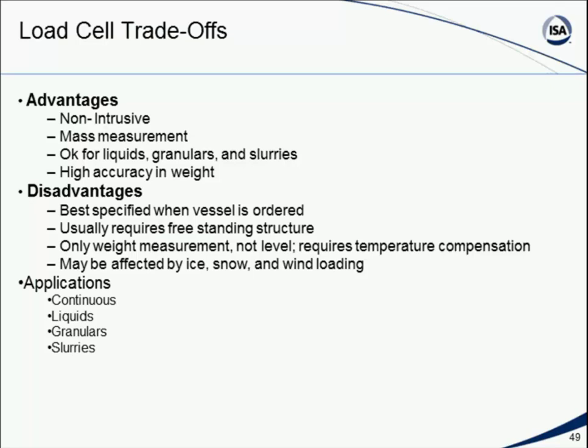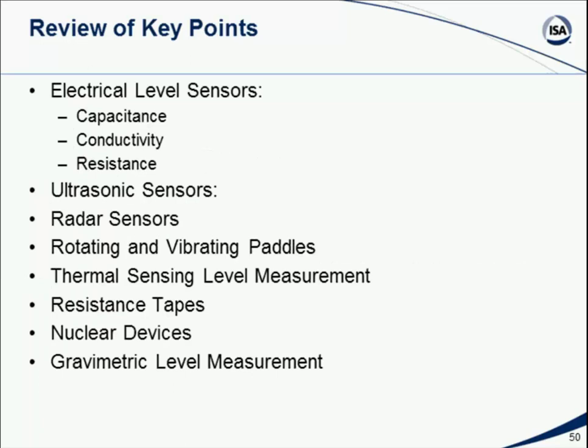So in some cases when we're using this type of measurement scheme, we have to use temperature compensation to correct for that. But it can be used in a lot of different applications, continuous process control for the storage of liquids, granular slurry. So this is something that you will see out there. It is used. All right, so we're at the end of the third section.